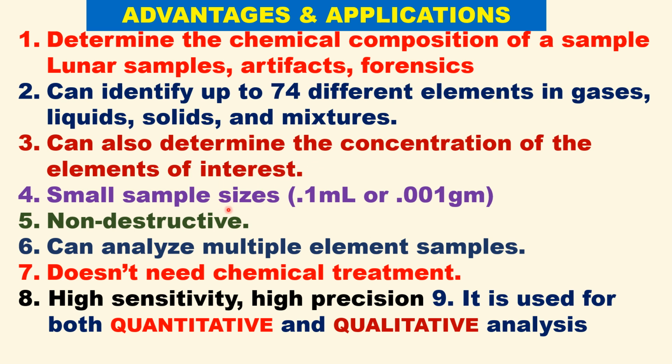The sample size is very small, so we need just 0.1 ml or 0.001 gram. So it is a highly sensitive, high precision technique, and it is a non-destructive method because the sample can be reused.